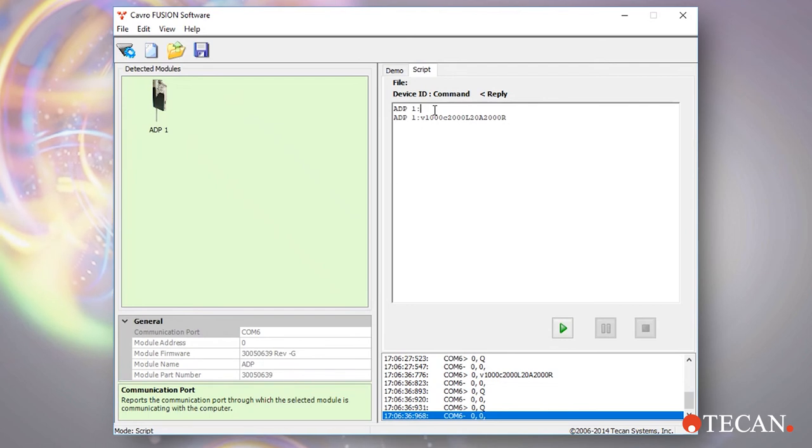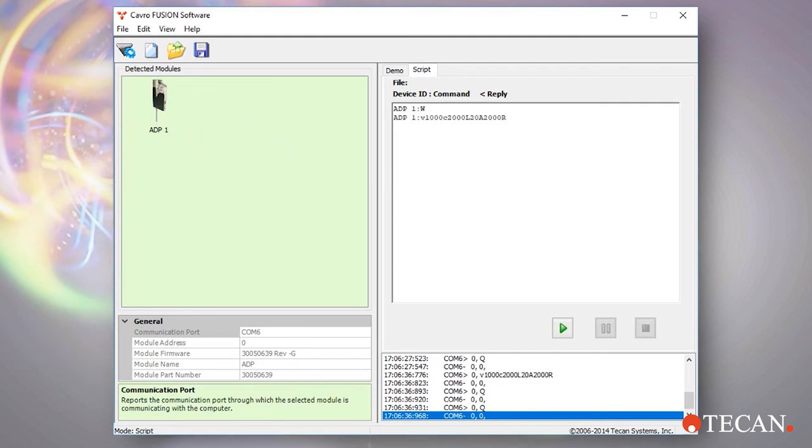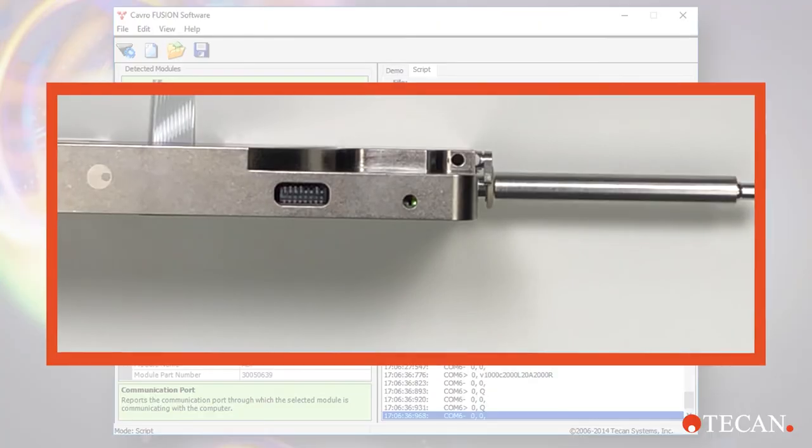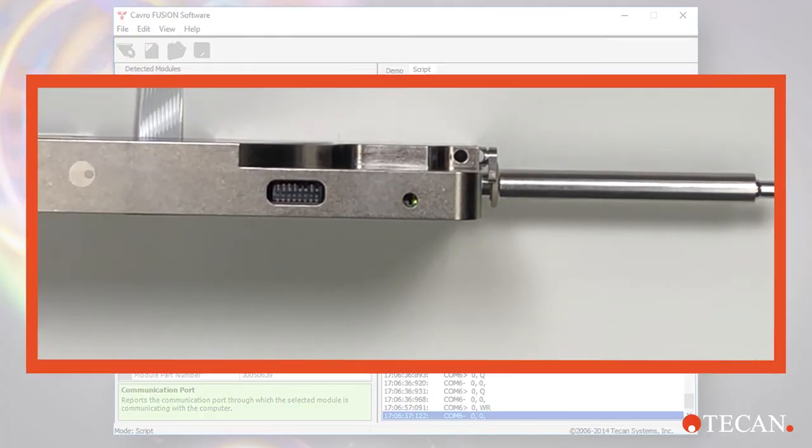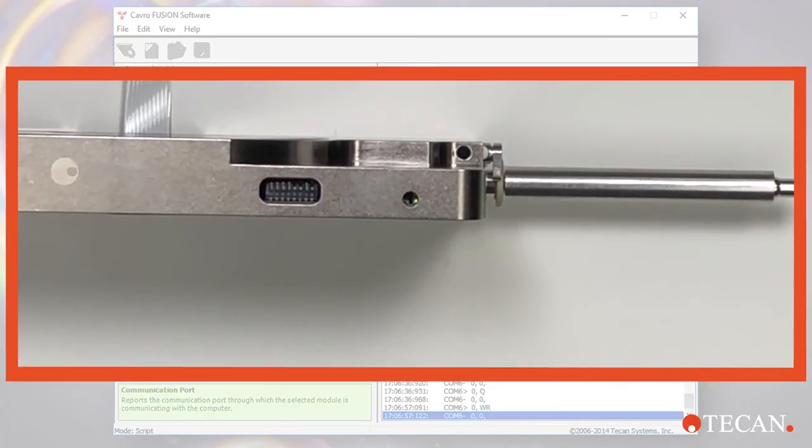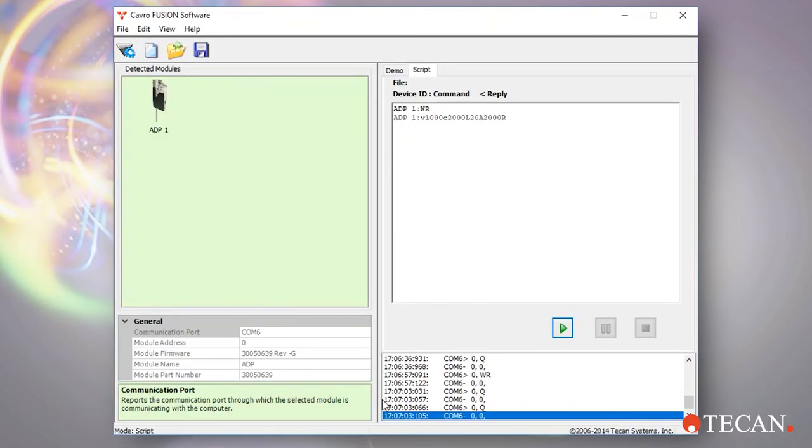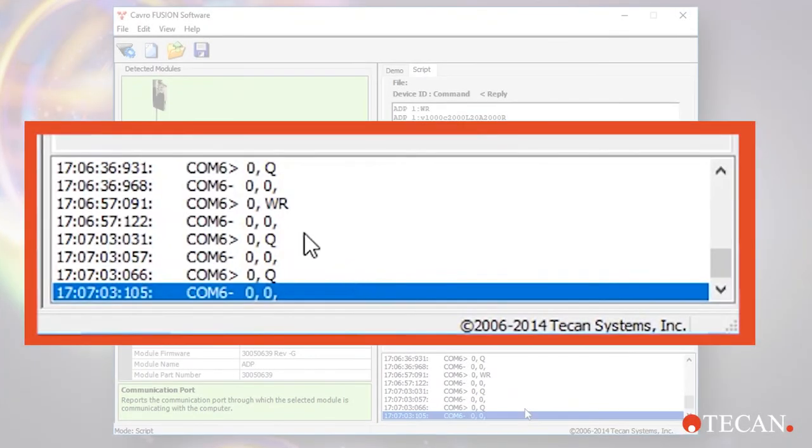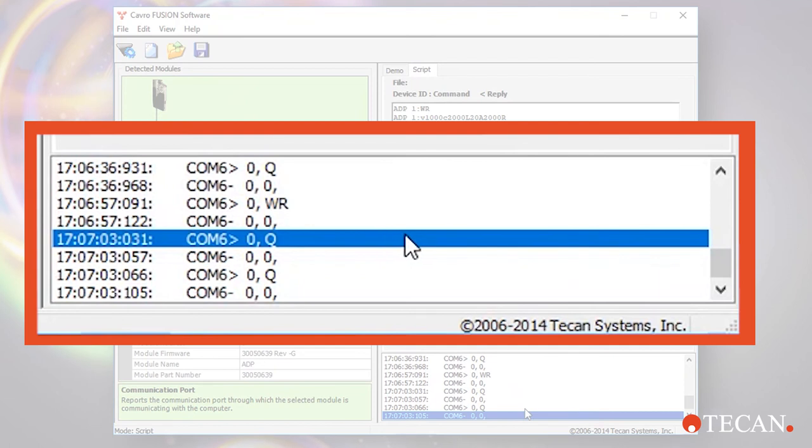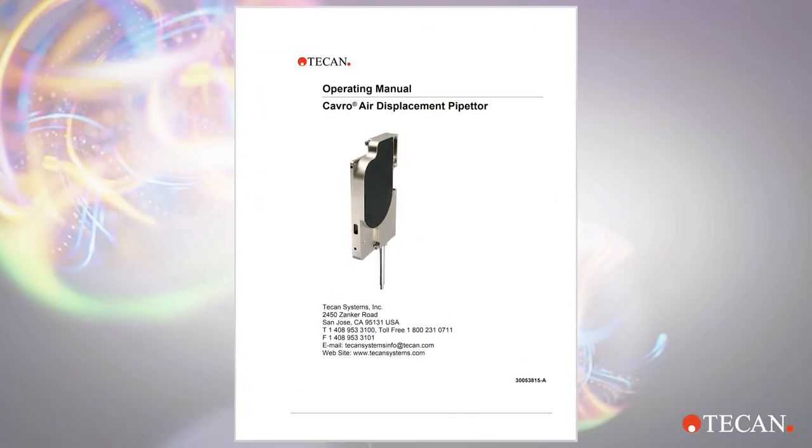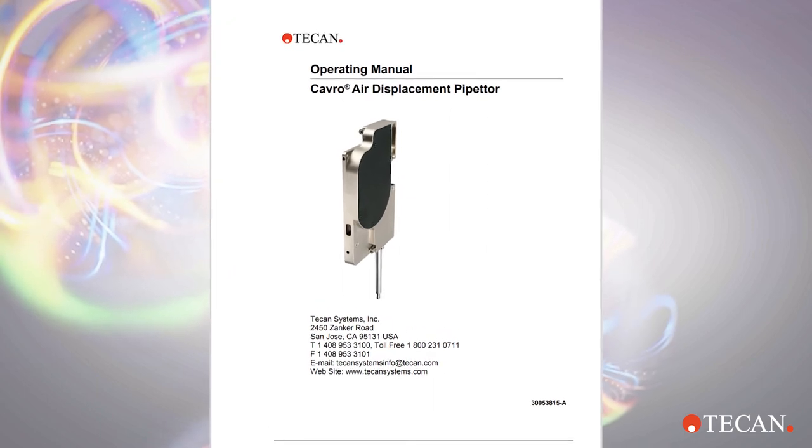Back to the ADP. Enter the WR command to initialize the ADP. That's capital W, capital R. Following initialization, the LED flashes green without the occasional red flashes. This indicates the ADP has been initialized and is ready to accept action commands. The log file displays and records to the computer all commands and is visible in the bottom right panel of the screen. Notice also that Fusion software automatically sends the capital Q or query command during command execution to monitor the pump status and any error condition at all times.